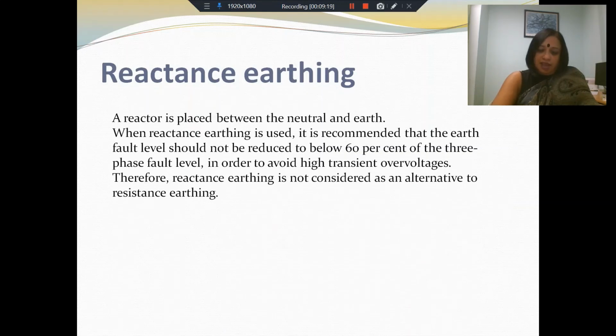Then you have reactance earthing. As is obvious, instead of placing a resistor between neutral and earth, in this case a reactor is placed between the neutral and earth. Now remember, there might be transient overvoltages across a reactor. So when you have a sudden fault and a sudden current rise, this can result in a high transient overvoltage. When the reactance is high, it might ultimately limit the fault current, but there might be high transient overvoltages when the rate of rise of current is initially very high, very abrupt. So it is recommended that the earth fault level should not be reduced to below 60% of the three-phase fault level. Otherwise, the transient overvoltages are so high that they are not likely to be very helpful. Therefore, reactance earthing is not considered as an alternative to resistance earthing. They might be used in conjunction with each other.